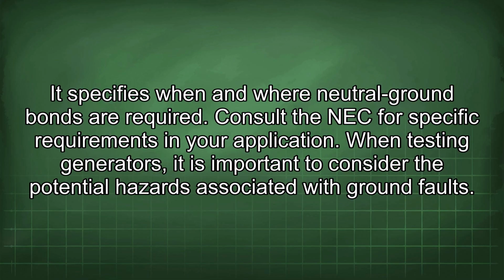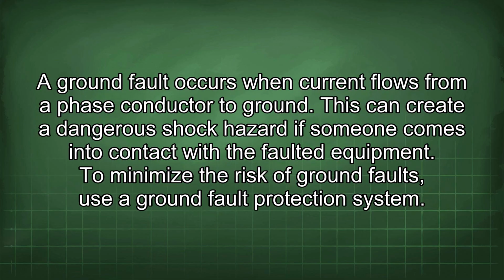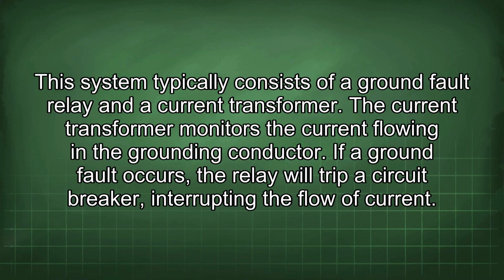When testing generators, it is important to consider the potential hazards associated with ground faults. A ground fault occurs when current flows from a phase conductor to ground. This can create a dangerous shock hazard if someone comes into contact with the faulted equipment. To minimize the risk of ground faults, use a ground fault protection system. This system typically consists of a ground fault relay and a current transformer. The current transformer monitors the current flowing in the grounding conductor. If a ground fault occurs, the relay will trip a circuit breaker, interrupting the flow of current.